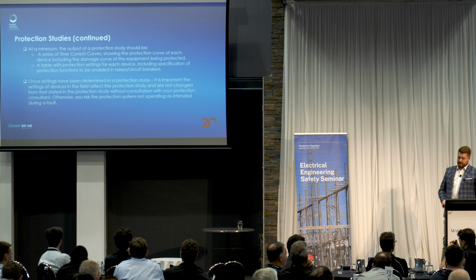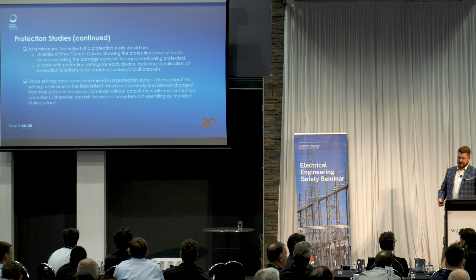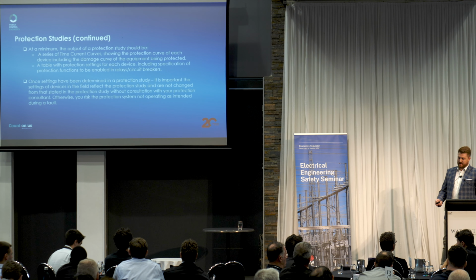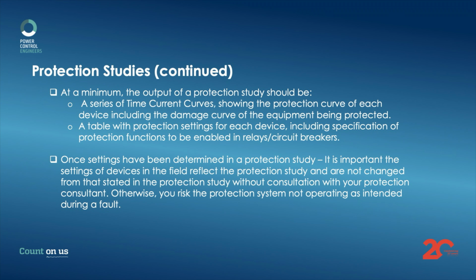At a minimum, the output of a protection study should have a series of time current curves showing the protection curve of each device, including the damage curve of the equipment being protected. So I've been asked by the regulator to include in this the damage curve of the equipment being protected. That sometimes apparently is left off. It's also important that the protection study has a table with protection settings for each device, including specification of protection functions to be enabled in relays and circuit breakers.